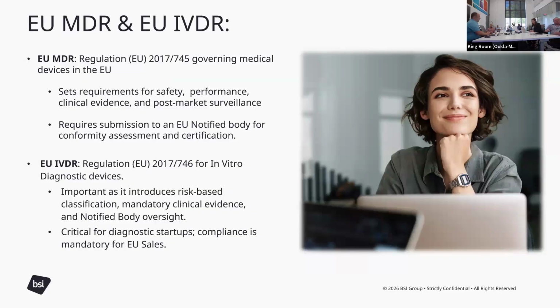So EU MDR and IVDR, these are the regulations in Europe to be able to sell your device, to get it certified. So the MDR is for devices and IVDR is for in vitro diagnostic devices. I mostly look at MDR, well, actually only look at MDR reviews. We're really looking at safety and performance of the device.